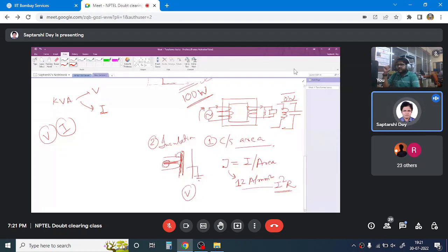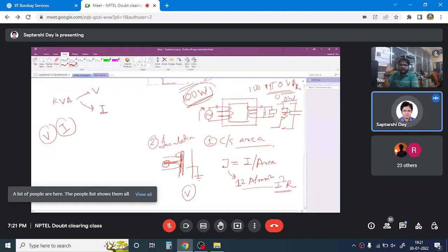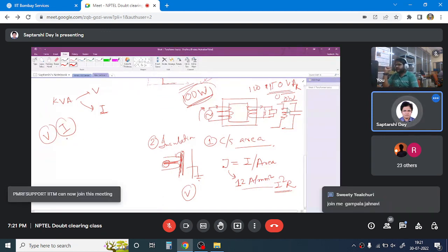That is why wattage is not the factor. Although you are drawing 0 watt, maybe you are drawing 150 volt ampere reactive. This requires some current, so the current is not 0. The winding does not understand whether there is active power or not, it only understands I-square-R loss, so it will burn down. Similarly, if you put high voltage, even with the secondary open, if the voltage is say 2 or 3 times the rated value, the insulation will fail. That is why these voltage and current figures are necessary.